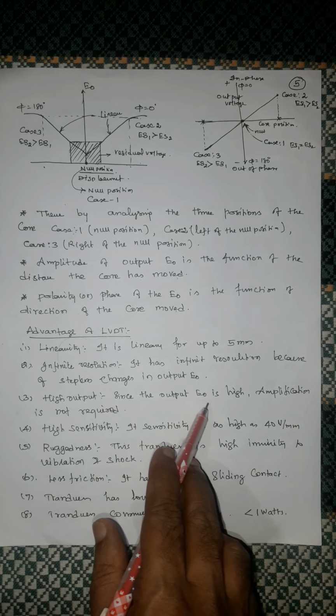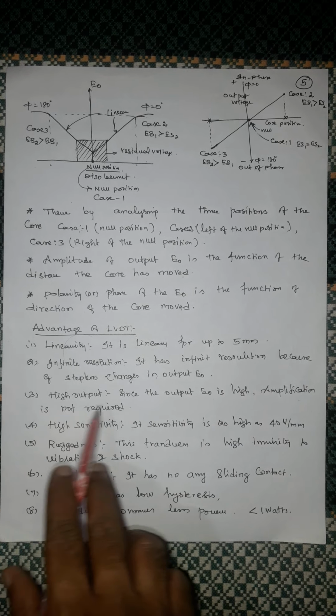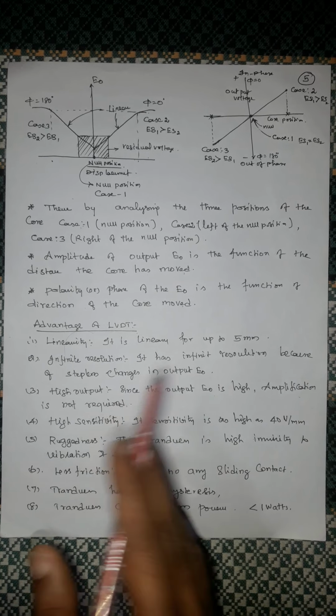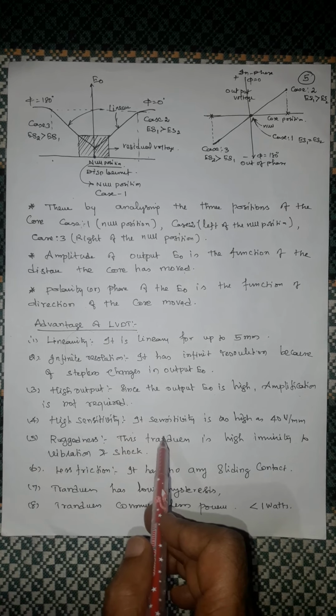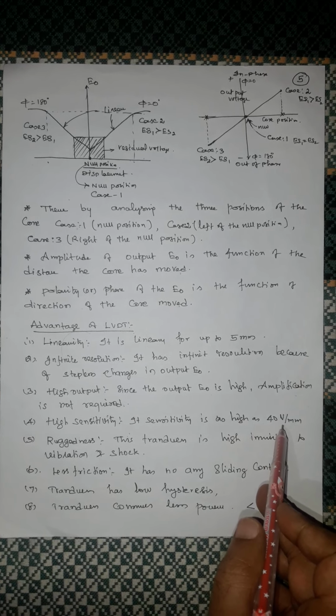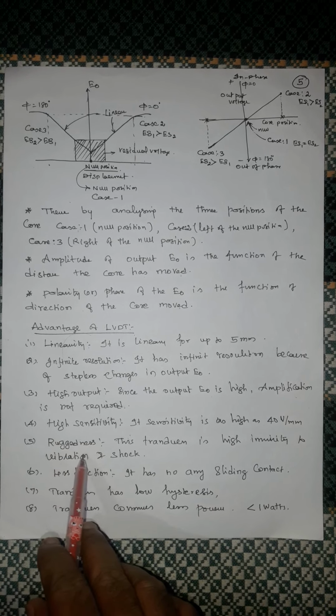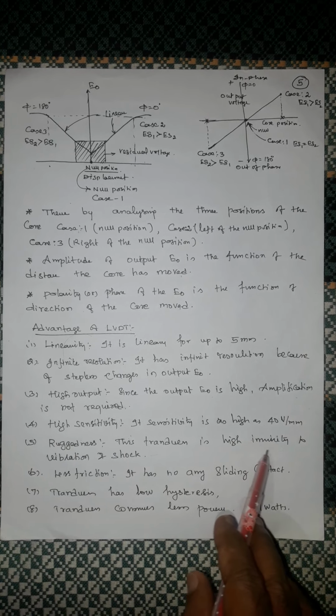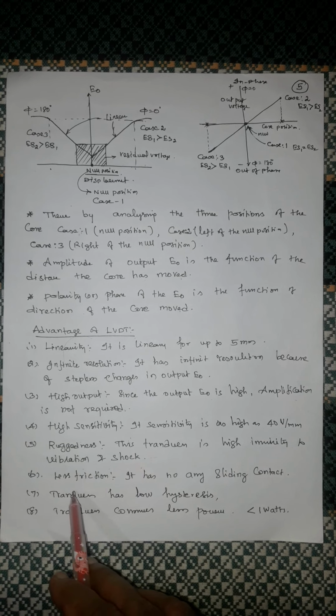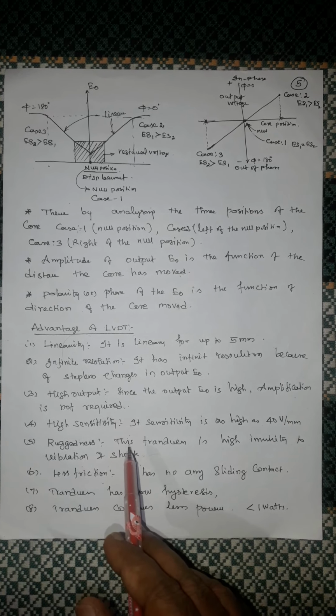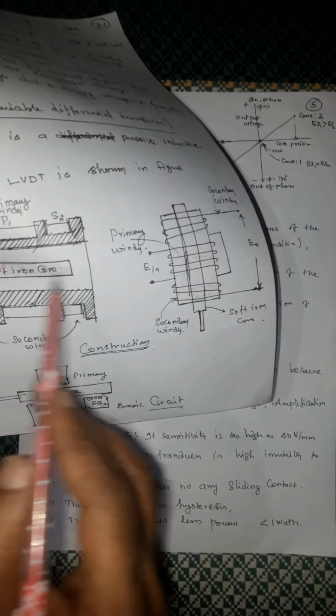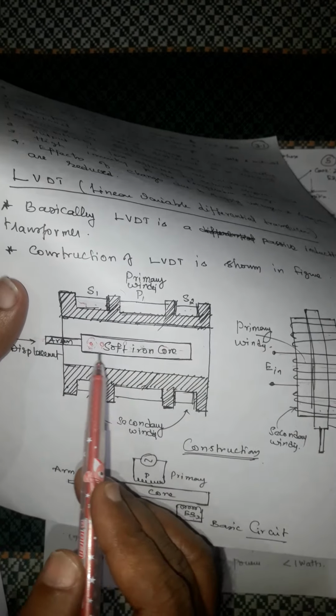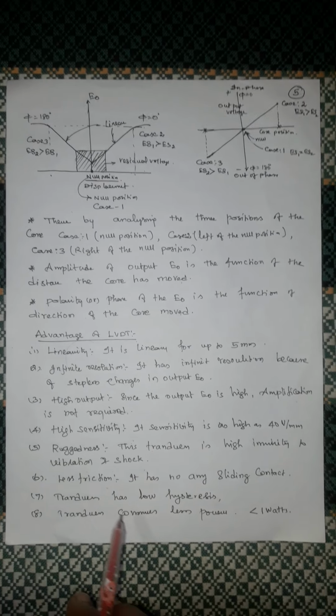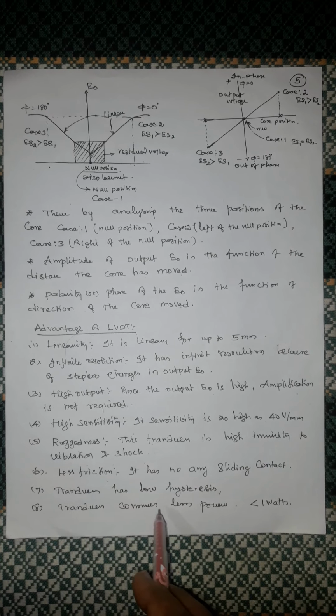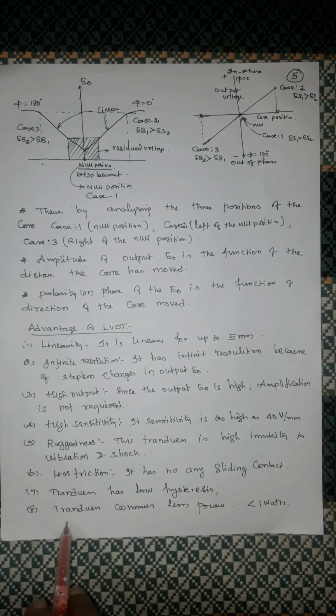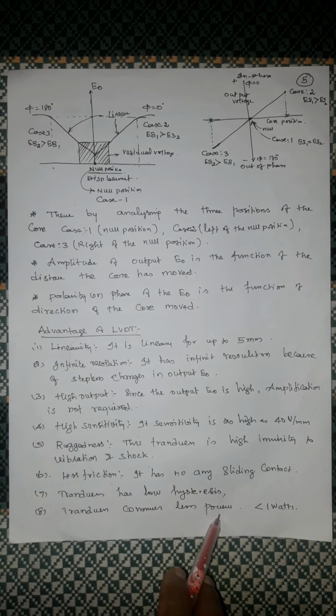High output: since the output E naught is high, amplification is not required. High sensitivity: its sensitivity is also high, about 40 volts per millimeter. Ruggedness: this transducer has high immunity to vibration and shock. Less friction: here friction is 0 because there is no sliding contact. The transducer also has low hysteresis, so hysteresis loss is less and it consumes less power.